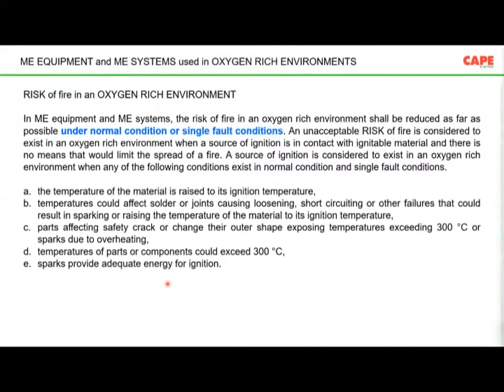The next requirement is the oxygen-rich environment. As I said, in an oxygen-rich environment the chance of a major fire is very high. So medical equipment used in that area must satisfy many special and specific requirements, such as the temperature of the material rising to ignition temperature. Before that, you are supposed to disconnect all these things. These requirements are necessary under normal condition or single fault condition. Single fault means an appliance is faulty. Even under that condition, these requirements must be met.